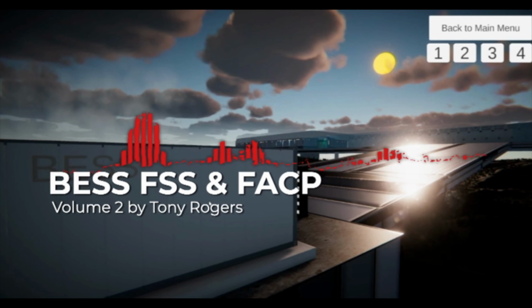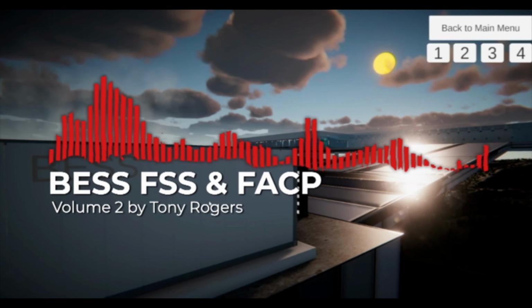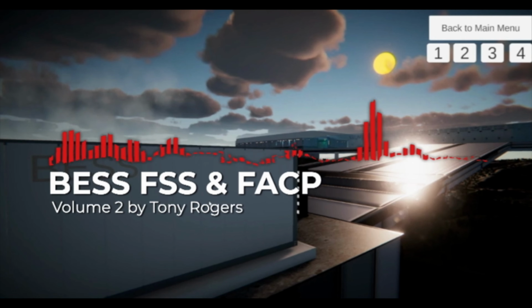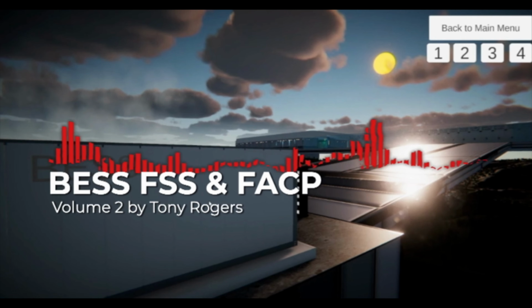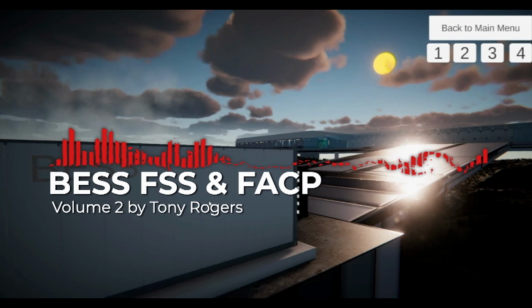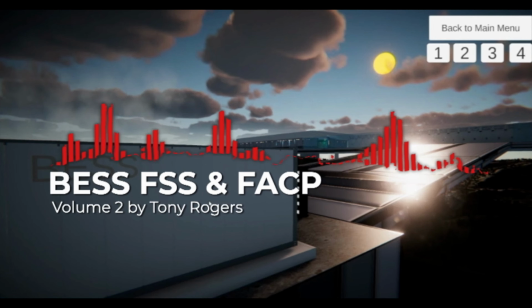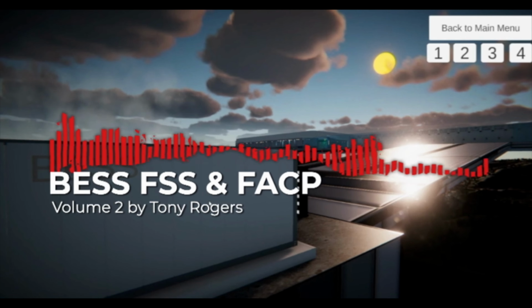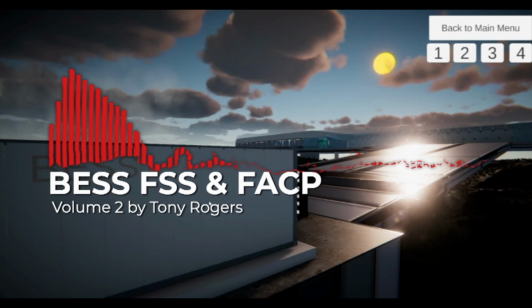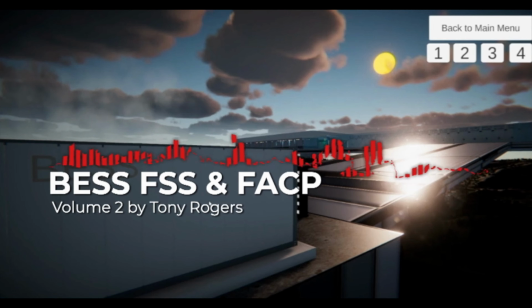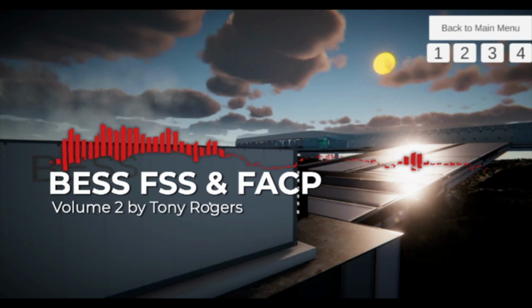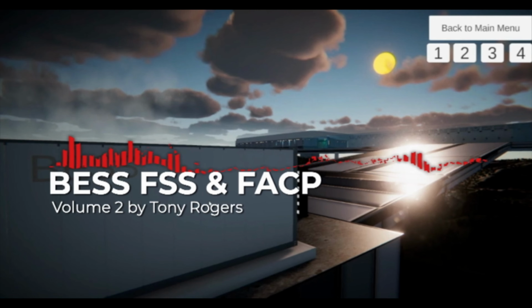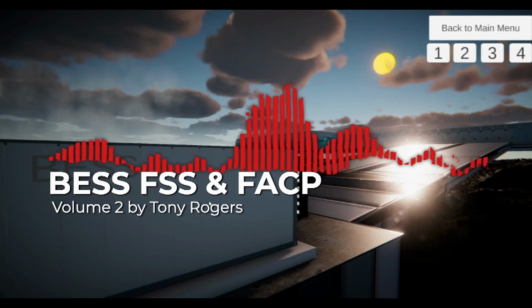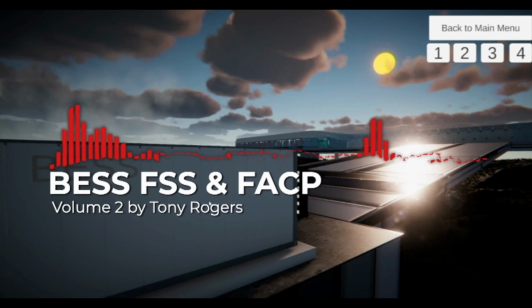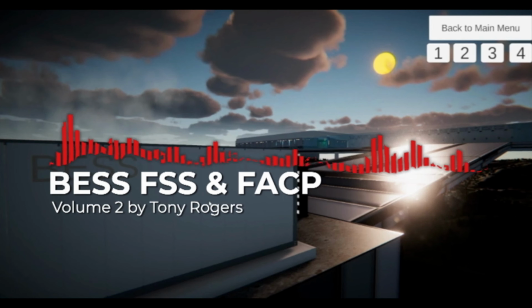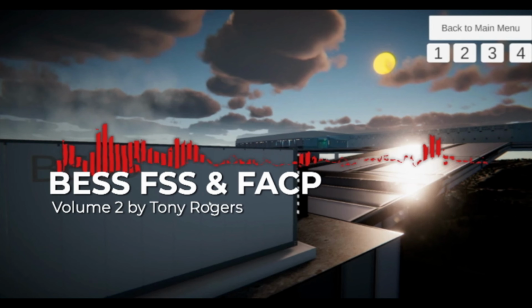Water tower placement considerations. Water tower placement is a critical aspect of fire suppression system design. Collaborating with the local authority having jurisdiction, AHJ, and fire marshal is crucial for obtaining valuable insights into prevailing wind directions and patterns. By analyzing these wind patterns, water towers can be strategically positioned to maximize the dispersion of water mist during firefighting operations. This collaborative approach ensures that water is effectively directed towards the adjacent BESS containers, thus mitigating the spread of the fire and aiding in its suppression.